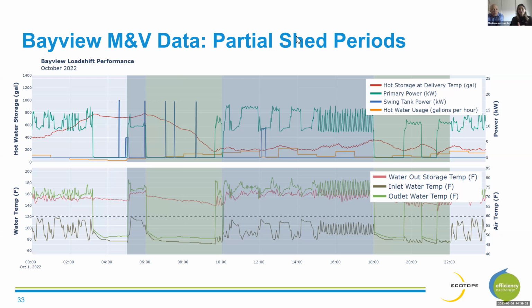So this is an even more aggressive schedule that we attempted in October of 2022. We have 2 4-hour shed periods. So this is quite a long time to be attempting to keep the heat pump off. We did this because we kind of wanted to test the limits of our load shifting capabilities, knowing that we do have a backup electric resistance water heater. So the tenants are always going to be guaranteed access to hot water, even though we are stressing the system.